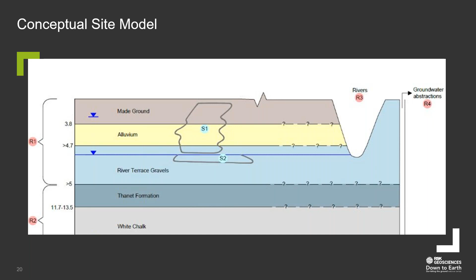So our first phase was to drill two what I will call test boreholes, but they are of the same design as the permanent boreholes, because open loop boreholes are very large and very expensive to drill. So you don't want to be drilling boreholes which can't then be used as part of your final scheme.